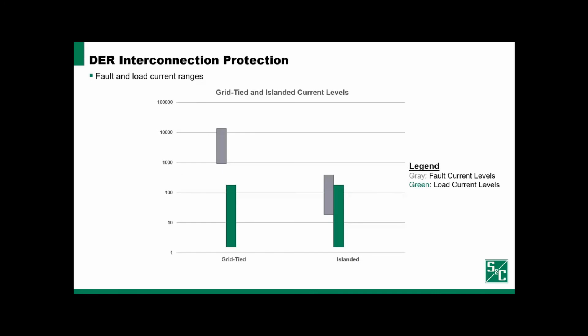One way I often like to represent this is looking at microgrid applications. As Saeed mentioned, microgrids can operate in either grid-tied or islanded configurations. They can operate in parallel with the bulk system or separated from it. And the fault currents that you can see in a microgrid can vary substantially between these cases. This plot I show is from an actual project that I've worked on in the past. And you can see very clearly here, in grid-tied situations, the fault current shown at the gray bar on top substantially exceeds the load current shown in the green bar on the bottom.